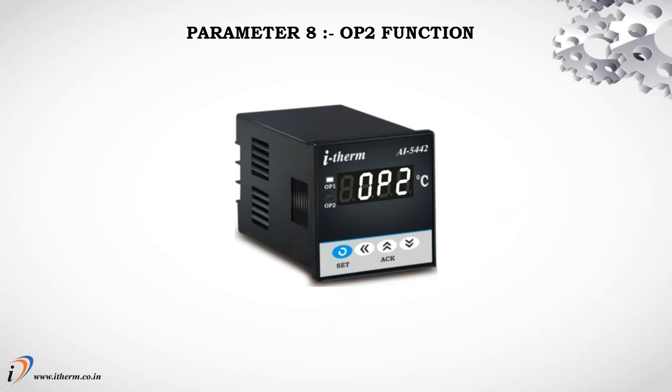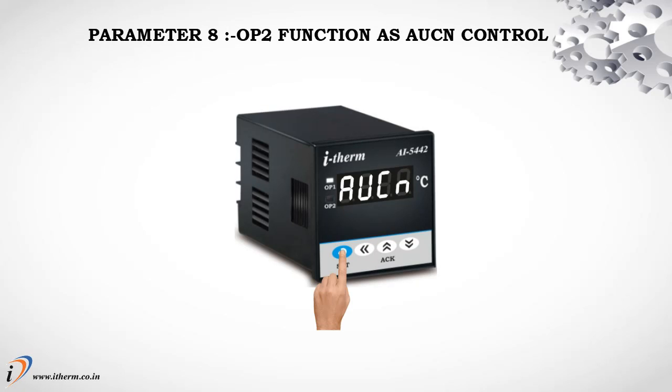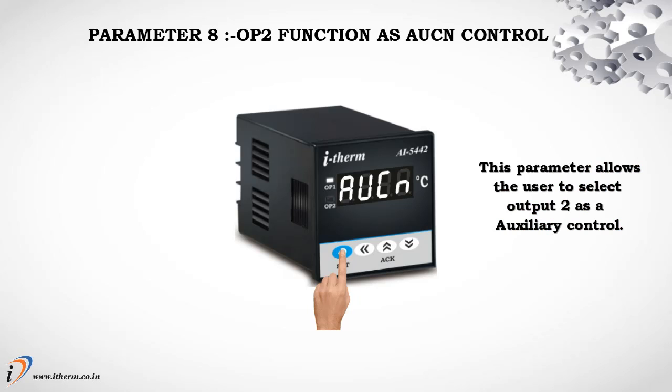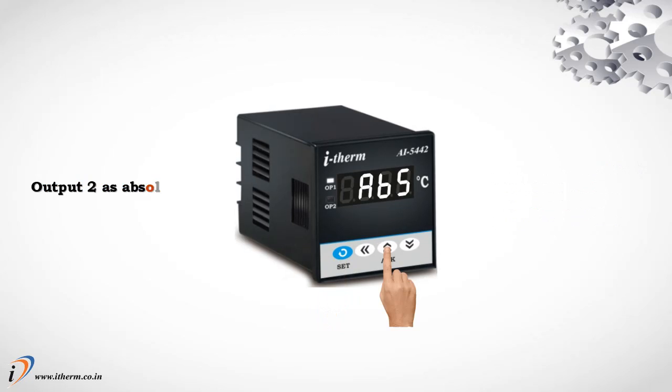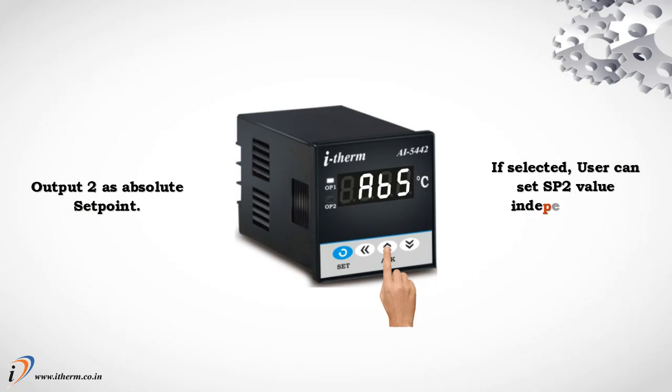Parameter 8. Output 2 function as auxiliary control. This parameter allows the user to select output 2 as an auxiliary control. Parameter 9. Output 2 as auxiliary control mode. Output 2 as absolute set point. If selected, user can set set point 2 value independently, irrespective of set point 1.